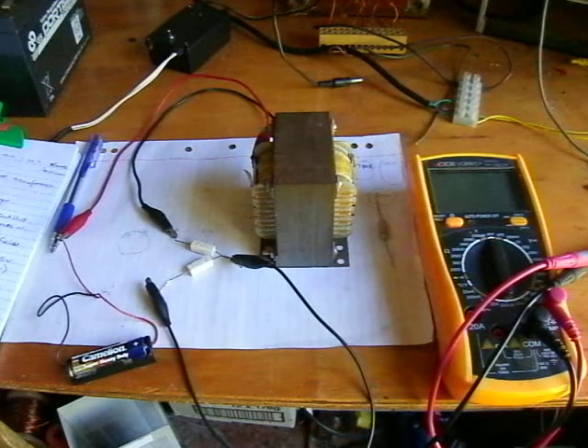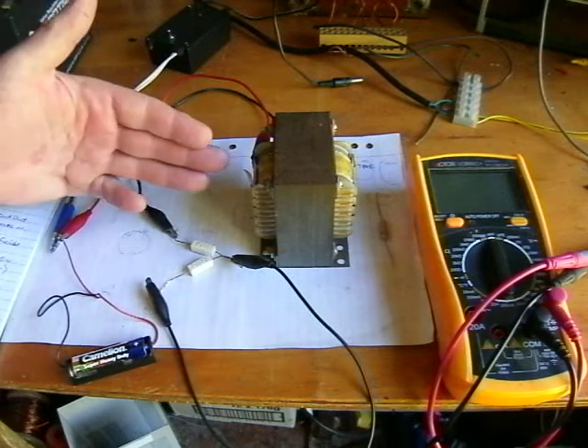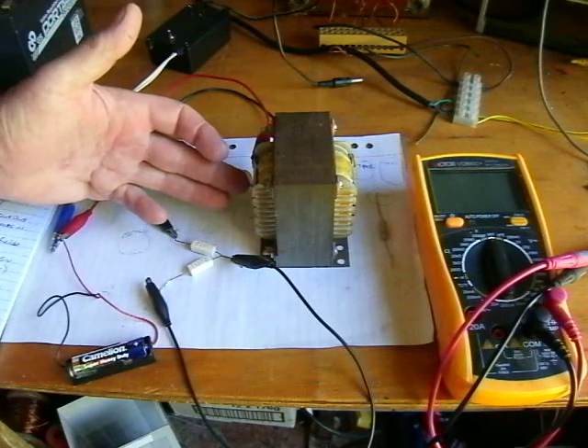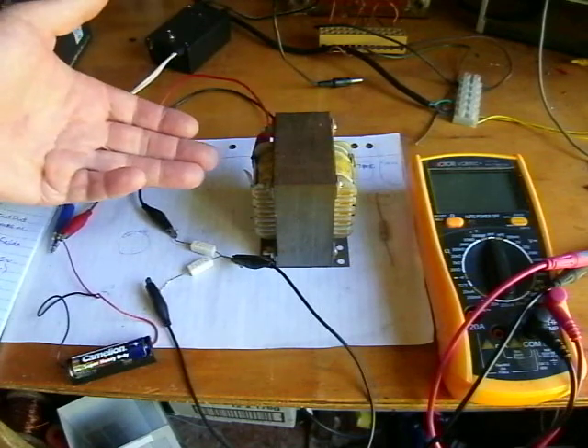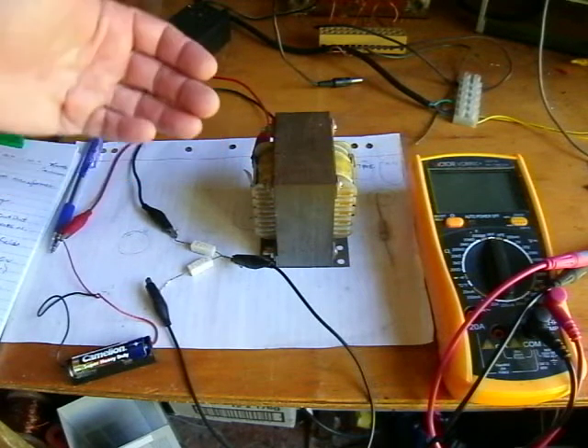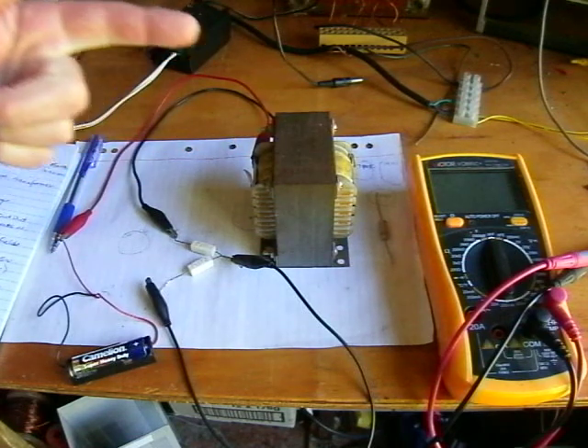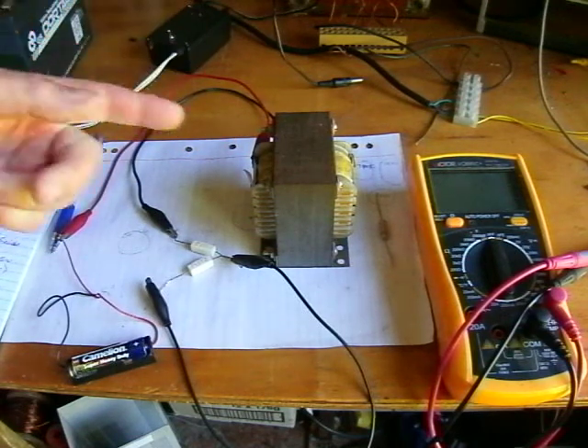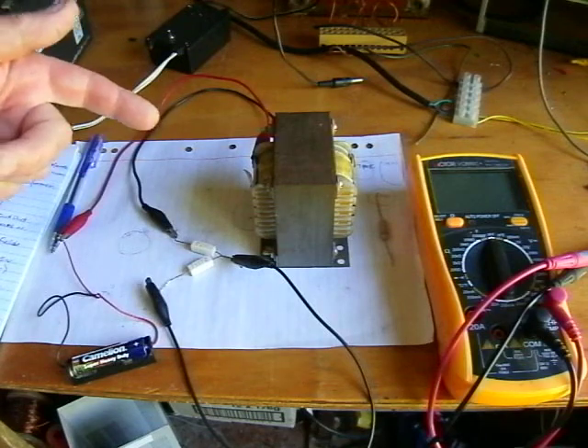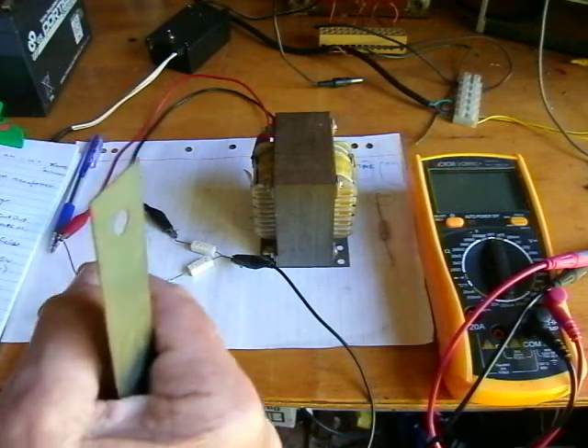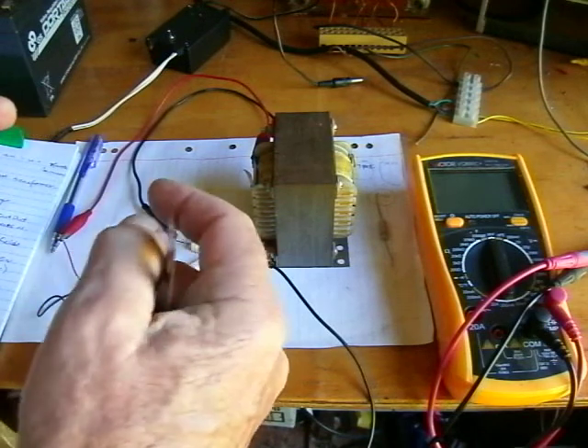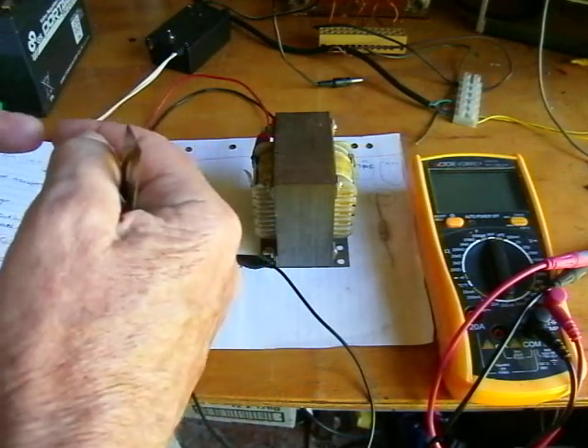Now when you see what happens when the 230 volts hits the winding, the moment the magnetism in the core builds a little bit, it produces a voltage in that winding opposing any current flow. So it's called a back EMF, back electromotive force. So the moment that magnetism builds, it just creates a voltage, and it's like only about 2 or 3 volts difference.